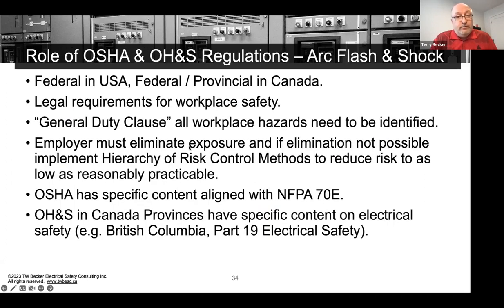So just briefly, OSHA in the US and OH&S in Canada, there hasn't been much change here, right? And I always quote, they have general duty clauses that these hazards should be identified. And then the employer needs to implement controls, eliminate exposure or implement other controls to reduce risk. So OSHA does have specific language aligned with 70E that hasn't changed. And in Canada, provincially, territorially, or federally, it's mostly the provinces and territories that'll have specific language because they're independent in OH&S regulations. And I just quote British Columbia Part 19 as an example, and it's electrical safety.